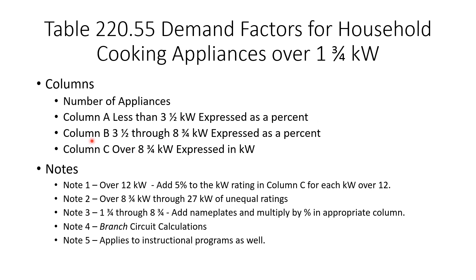Column B covers appliances between three and a half and eight and three-quarters kilowatts, also expressed as a percent. Column C covers anything over eight and three-quarters kilowatts, and it's expressed in kilowatts — not percent — which is what can be confusing.